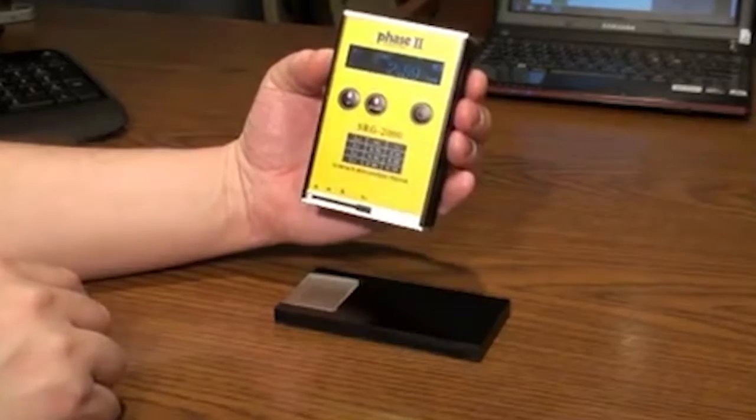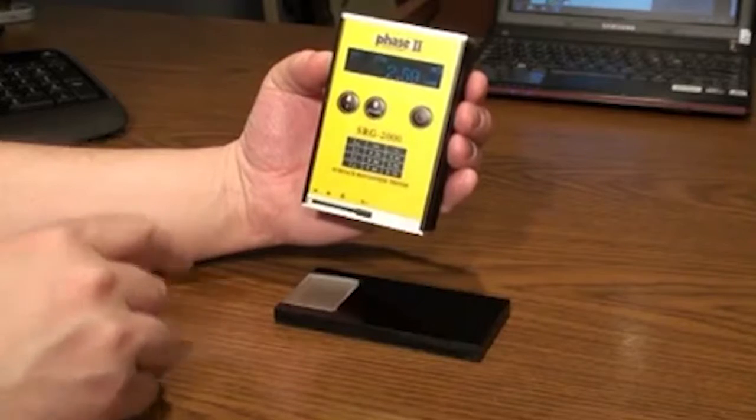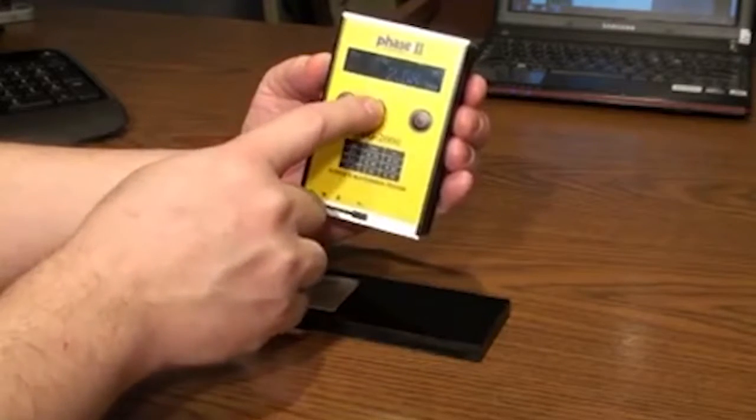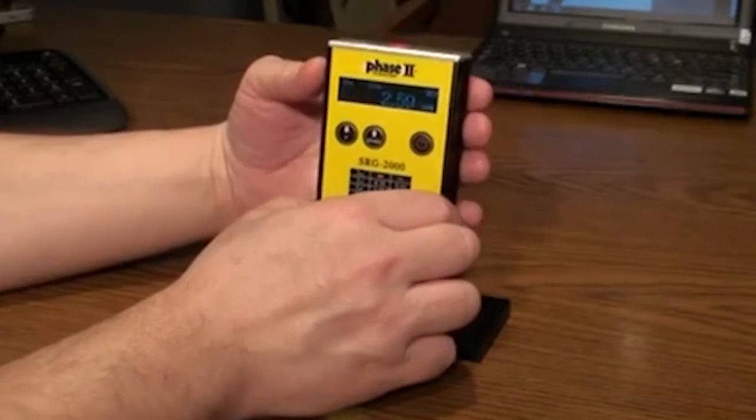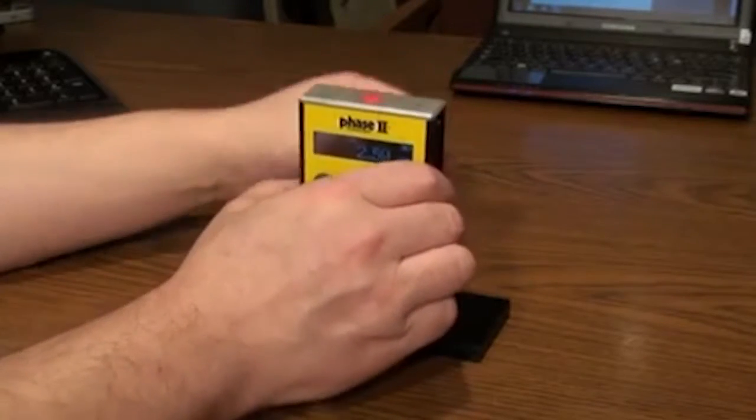If this value doesn't match your test sample, then you must adjust it by pressing the up or down arrow buttons on the keypad. Press the start button on top and the unit will begin calibrating itself.